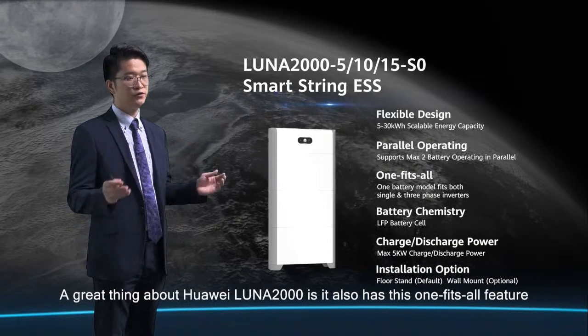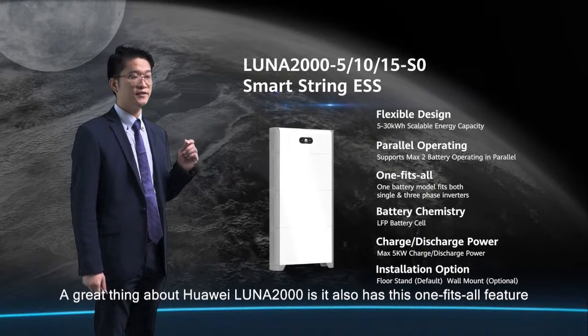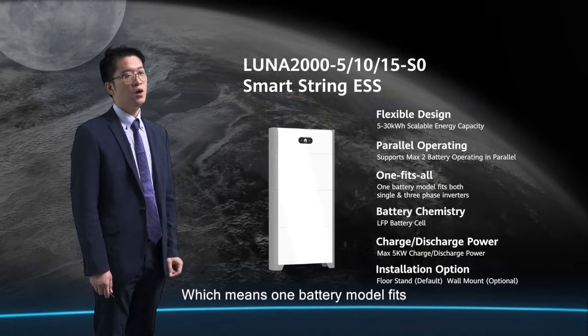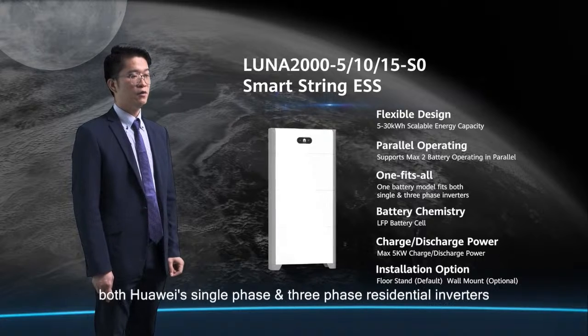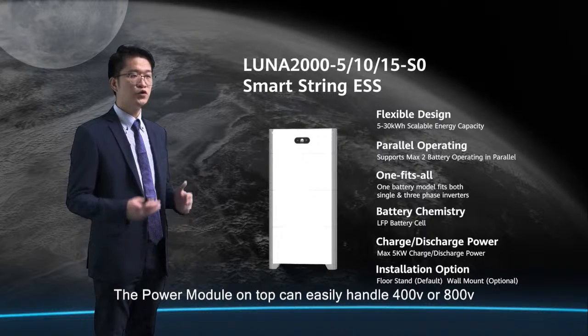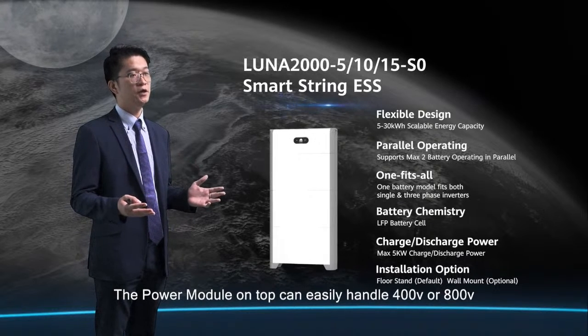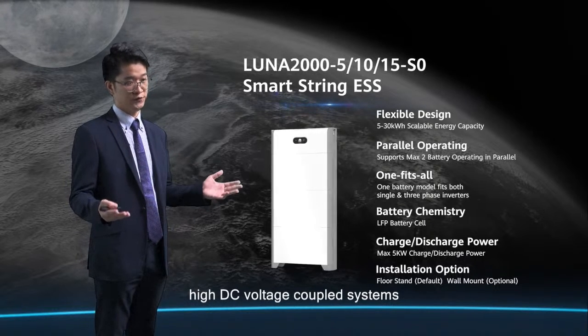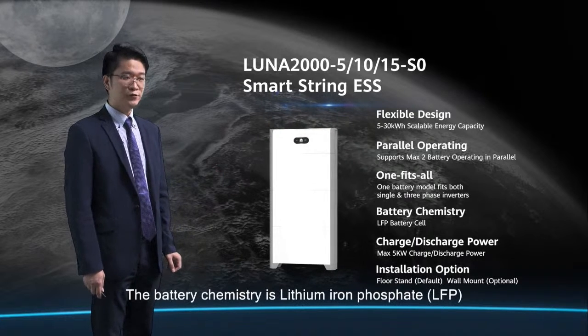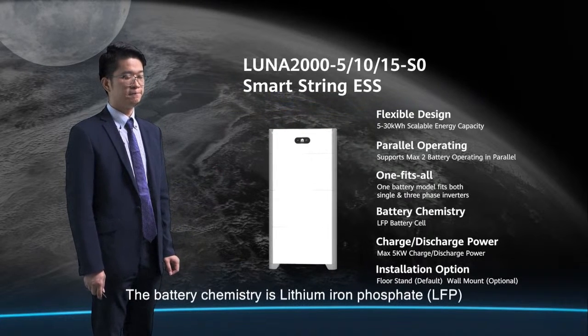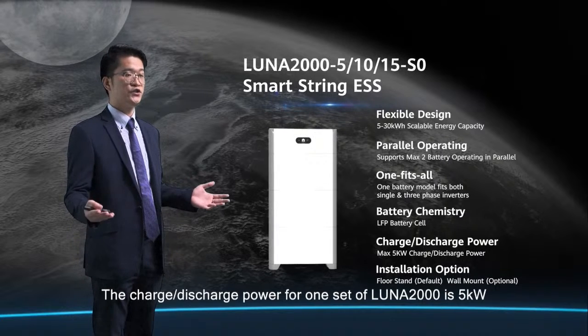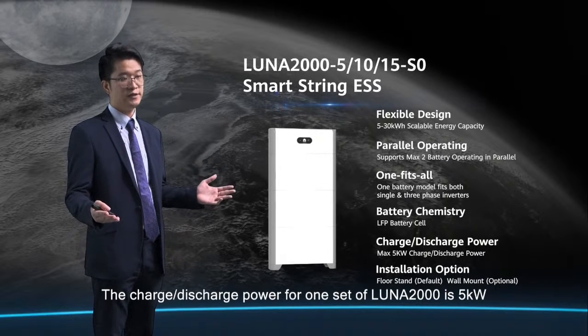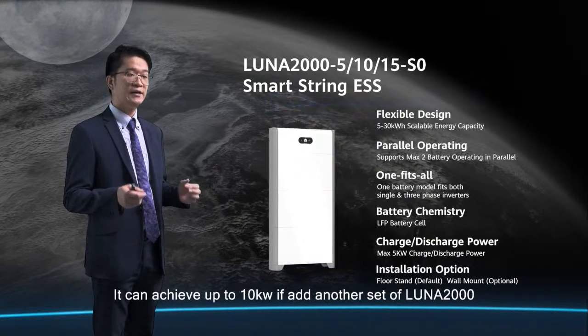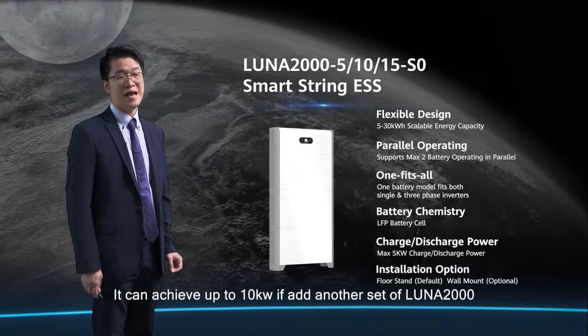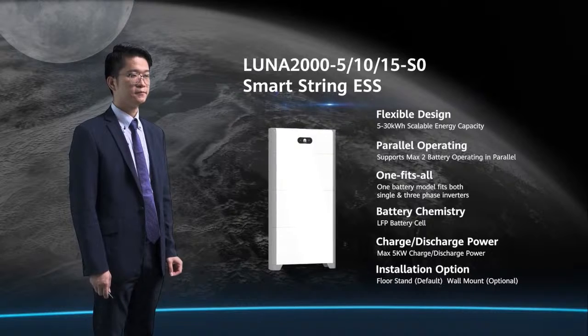A great thing about Huawei Luna 2000 is it also has this one-fits-all feature, meaning one battery model fits Huawei's single-phase and three-phase inverters simultaneously. The power module on top can easily handle 400 or 800 volt high DC voltage coupled systems. The battery chemistry is lithium iron phosphate. The charge and discharge power of one set of Luna 2000 is 5 kilowatts, but it can achieve up to 10 kilowatts if we add another set of Luna 2000.